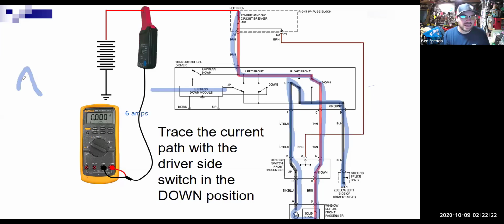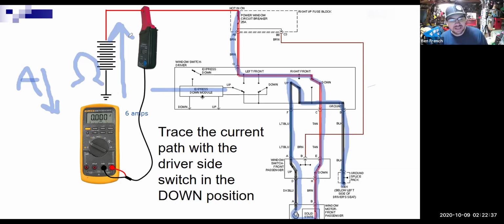If the current flow, the amps are still too low, that means the resistance has to be too high. So I'm still in there doing voltage drop tests, but I'm not expecting to find an open circuit. I'm expecting to find high resistance somewhere. So it's a little bit of a different breakdown.